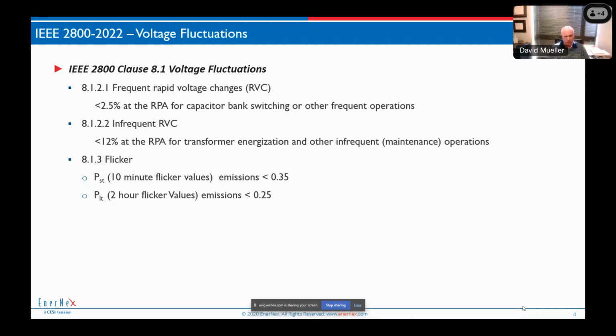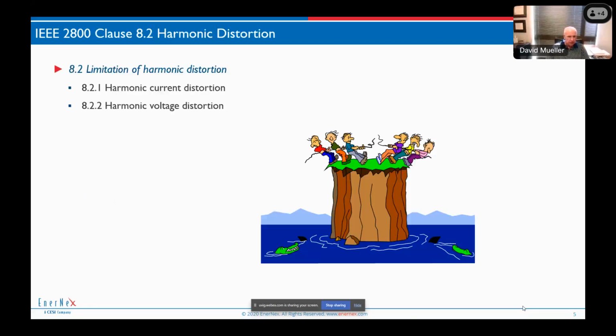We're only going to allow a plant to use a portion of the limit. We've done flicker evaluations for plants. We never get close to these values. The operation of wind turbines, the operation of inverters is much more smooth than this. So flicker is not normally any sort of an issue. We have seen it with older style equipment on weaker systems, but that's not the norm.